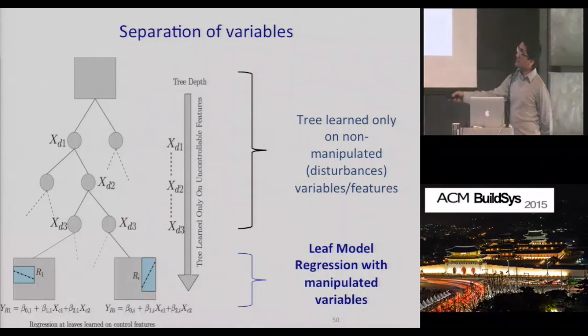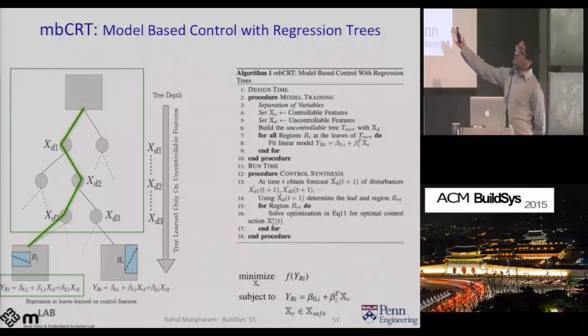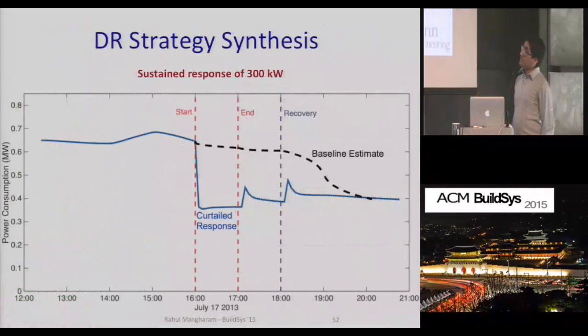So that gives us a linear model of that building. And then we can run our optimization to minimize the power of that. And then we can execute the different strategies that we would have for the different variables for chilled water, for the airflow, for lighting, et cetera, and synthesize curtailments that are able to achieve a certain required power level of curtailment.